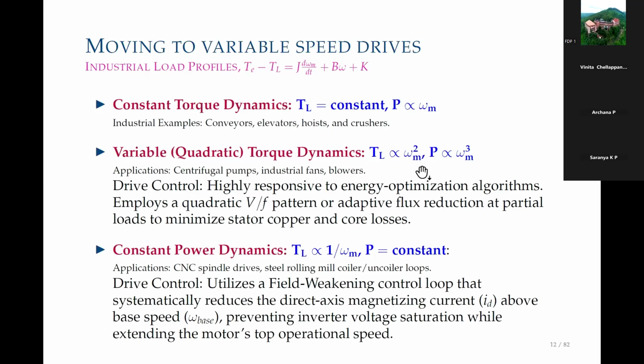If you look here, when the speed reduces by 2, we can see that the power reduces by 1/8. So these optimization algorithms can minimize stator copper loss and core losses. We also have constant power cases where the load torque is inversely proportional to the speed.